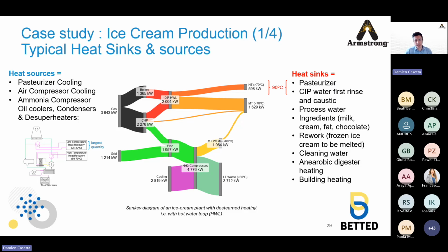In this Sankey, it's the high temperature heat which is then used directly to feed the medium temperature hot water loop at 60, 70 degrees. But you can see that all of that heat lower than 30 degrees here is wasted. But at the same time, we have heat sinks, so heating needs in this plant. Again, on pasteurizers, on cleaning in place, process waters, ingredients, rework, cleaning water, digesters, but also building heating.